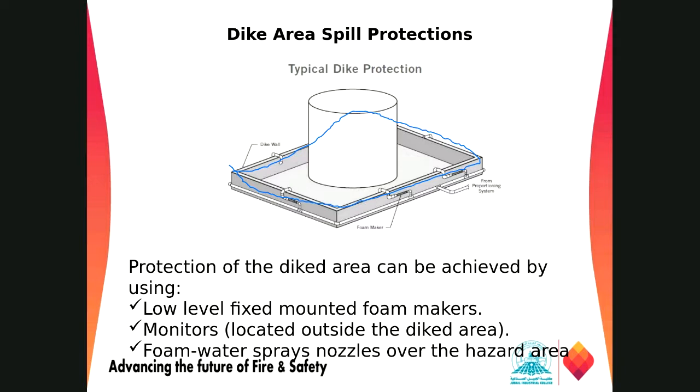So this dike can contain fuel to a minimum depth of 1 inch, or even higher. So we need a dike to protect our areas. How can we protect the dike with the foam system? We have low level fixed mounted foam makers, right? If you can see, we have foam makers here. This is the foam maker. It will discharge the foam solution into that area if there is a fire, and it will protect against the fire.